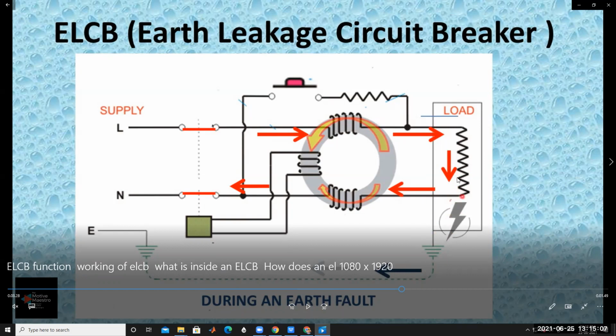For example, 2 amps of current is flowing as leakage current, and the remaining 3 amps is flowing through the neutral wire through this coil. That means here the coil is excited by 5 amps, and this coil is excited by only 3 amps. So that's why there is a difference between the currents and also a difference between the fluxes.